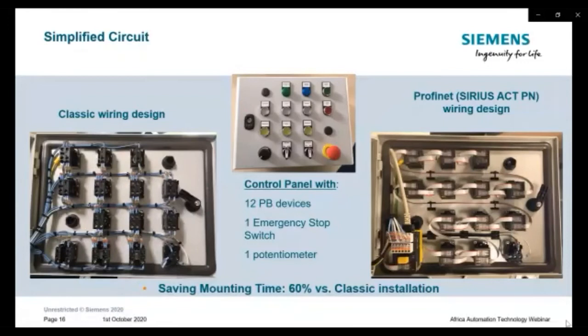Let's have a quick look now at the savings by figures. You see on the left the classic wiring design and the PROFINET wiring design with open door. Here you see the design with closed door, including 12 push-button devices, one emergency stop switch, and one potentiometer. So the saving in mounting time versus classic installation was 60% with this small application. This 60% saving in mounting time. Well, it depends, of course, on your hourly rate how many dollars you're going to save, but trust me, if you look at the number of control panels you're going to build per year, it's a reasonable amount of money.